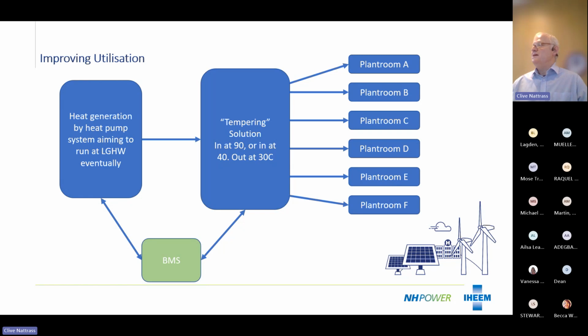So the idea is you go and convert plant room A, if that's what you're going to do. You take out the heat exchangers in your air handling unit and replace them with ones capable of doing 40, 45 degrees, but you run them at 80 degrees. There's nothing to stop you doing that. It allows you to convert and run at higher temperatures until you reach a point where you can start to reduce the temperatures, if not wholesale, then in part.